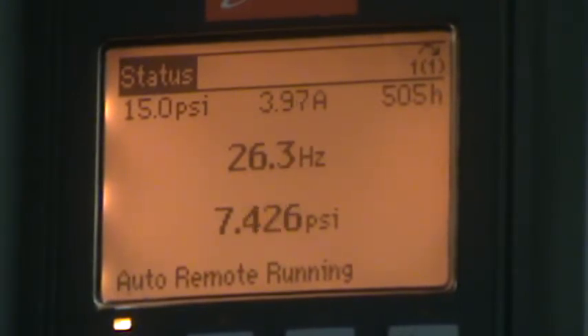They're not incredibly fast acting, and it's by design. It's the way we have it programmed. If we program the controller too quickly, you end up overshooting and then undershooting, and you're really kind of searching, with a large number of apartments and not really big valves with high volume. With them opening and closing, I'd rather have them go a little slower. It's better for the pump, it's better for the motor than to be constantly up and down. What you'll probably find is the motor will find that sweet spot.